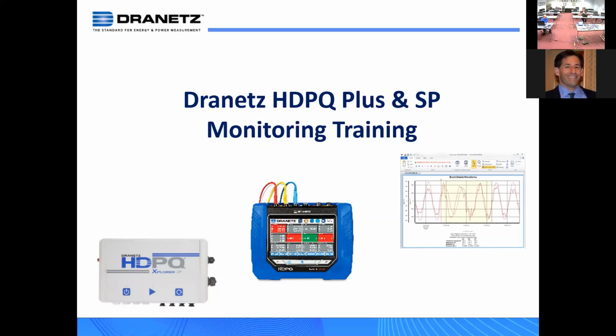It's in a remote package, but has the benefit of being able to power from the phase that you're measuring. So these are 1,000-volt instruments. However, the SP has a little power supply input on the left where you can jumper over and power the instrument from anything you're measuring at 600 volts and less. So it's a 1,000-volt instrument, but the power supply is only rated at 600 volts AC and 500 volts DC. That's one of the big differentiating features between the portable package and the SP package.